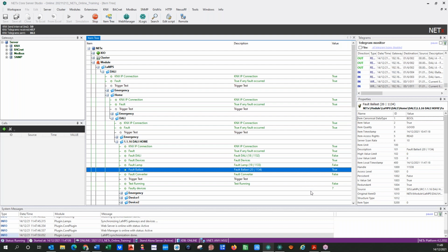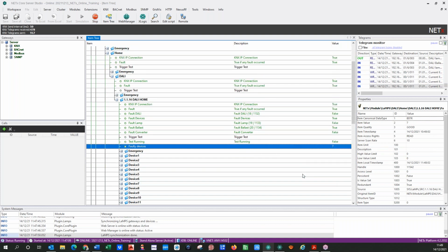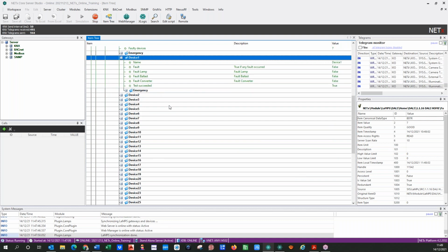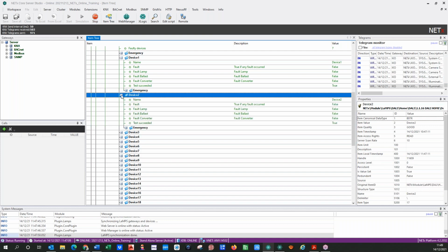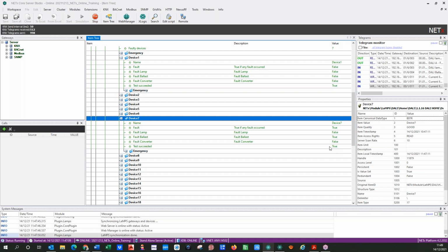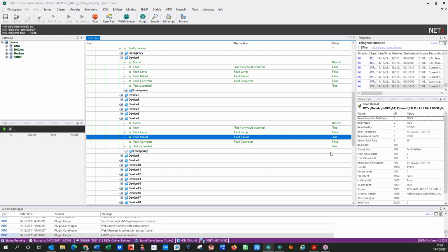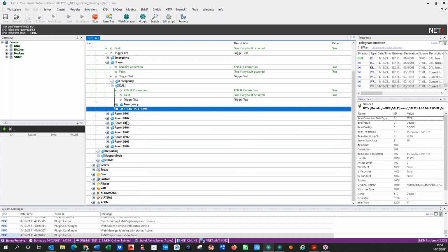In which device? Only one device: number 7 is the only one with a fault. I have defined 33, so you can see the 33 here. If I show you device number 1, it's not faulty. The test succeeded. Device number 2, exactly the same. But if you go to device number 7, you see that there is a fault in the ballast. So we could do the test, but we found a ballast fault. And you get this information automatically with only a small amount of time invested.